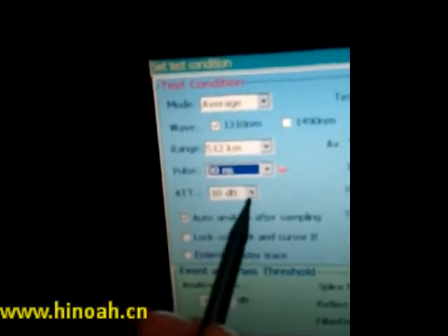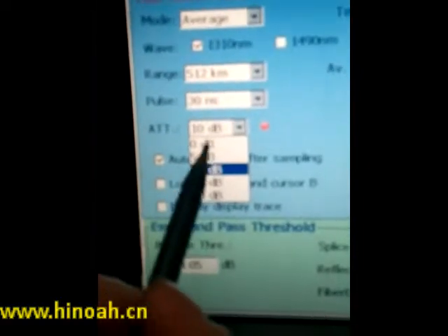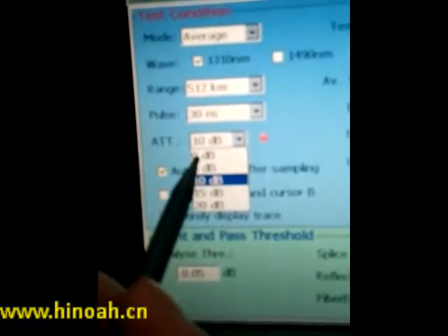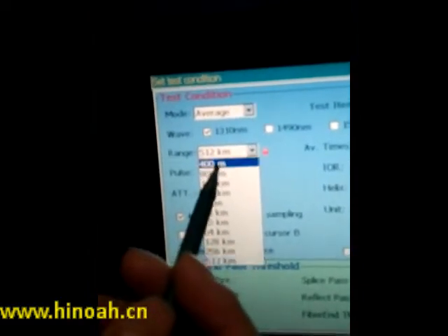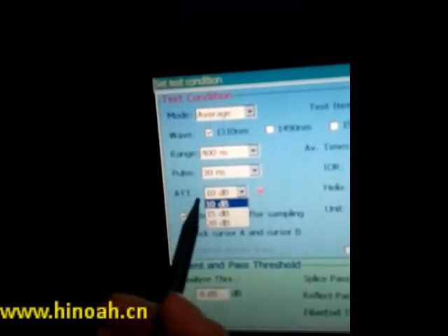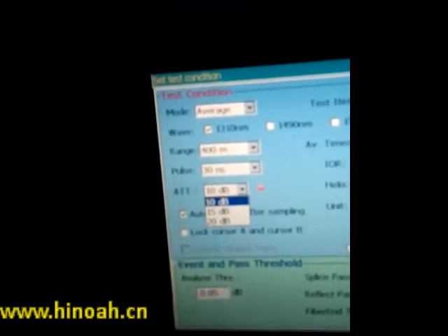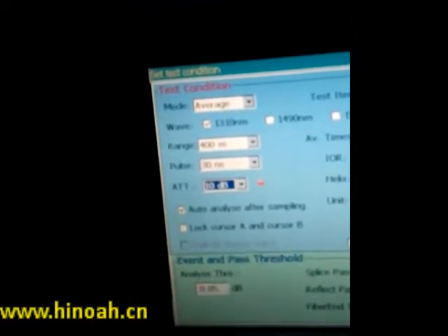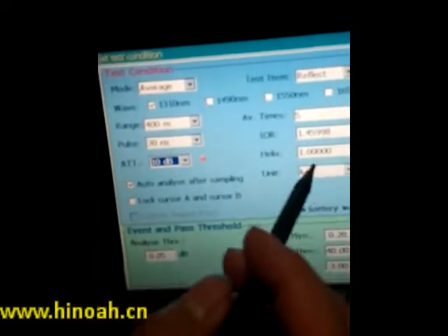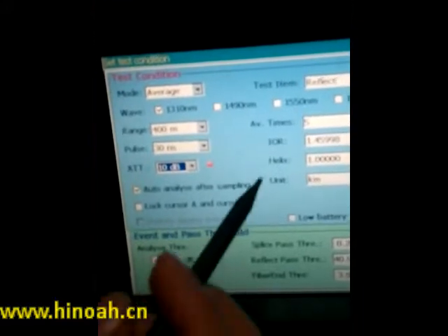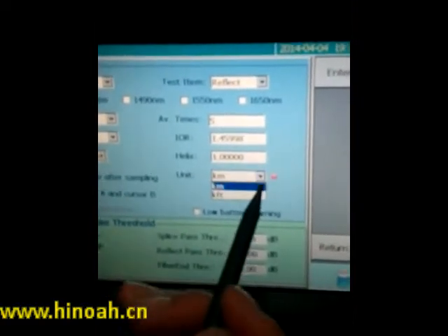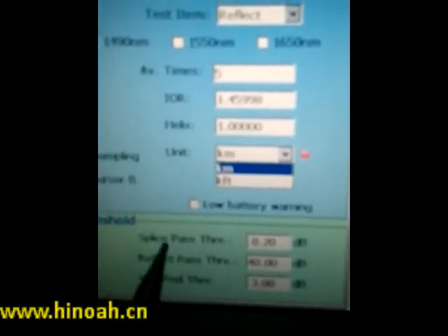The attenuation setting will also vary — it can be from 0 to 20, or from 10 to 20 depending on configuration. Besides this, there are other setup parameters such as Average Time, IOR, Helix, and Unit. For the Unit setting, you can choose between kilometers and kilofeet.